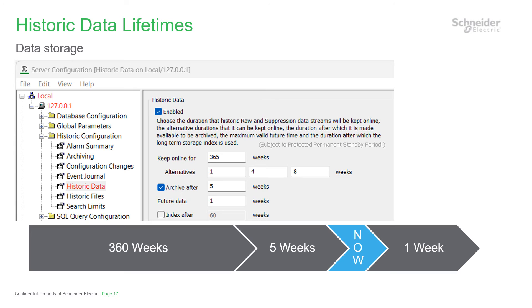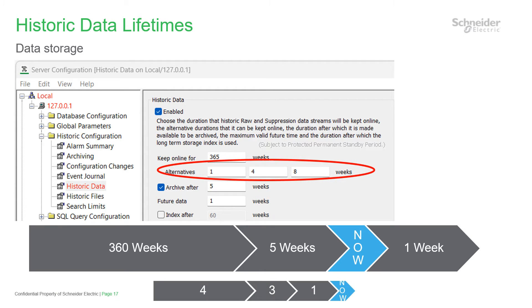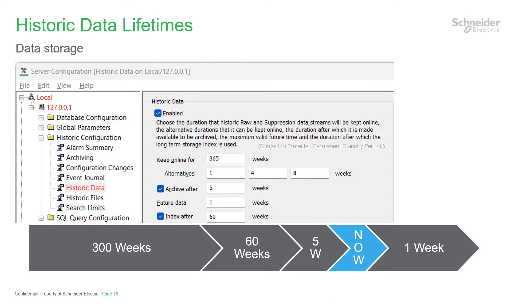For historic data from points and accumulators, all points have got the same online and archive period — here they're set for 360 weeks plus 5, total 365 weeks. For GeoSCADA 2023 there are new alternative maximum lifetimes available for point configuration. These shorten the life for selected points, perhaps to be used with points with a higher data frequency. For this point historic data there's another setting called Index After. By using this you can reduce the system startup time and reduce memory use. This feature is mainly effective for large systems and you may wish to contact the support team for advice before it's deployed. You could try without it first.